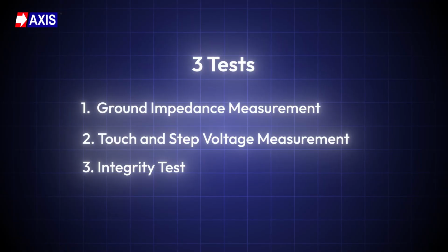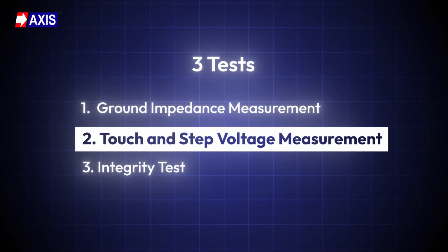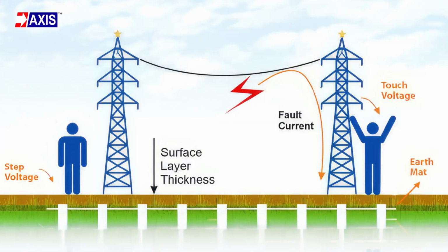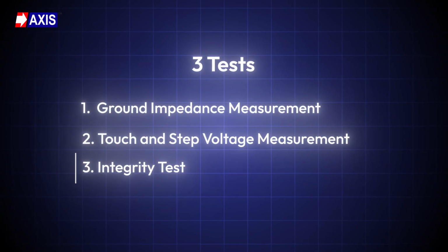The second test is the touch and step voltage measurement. A known current is injected into the ground grid from a remote electrode, and the resulting voltage gradients are measured across the yard. The actual touch and step voltages are then determined by scaling up for the full substation fault current. The third test is the integrity test. This test verifies that all connections are sound and checks for broken conductors, high resistance joints, or any damage to the grid that may have occurred during construction.